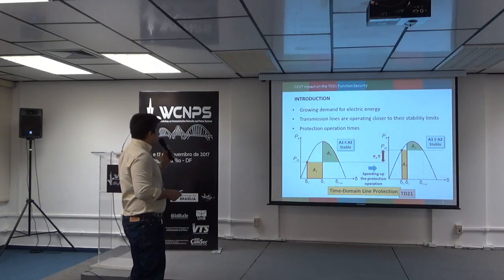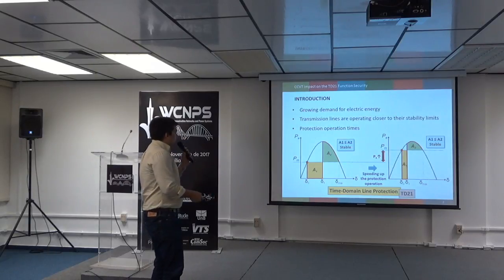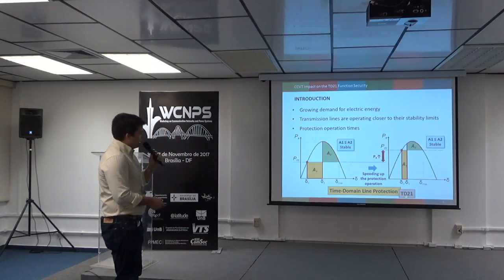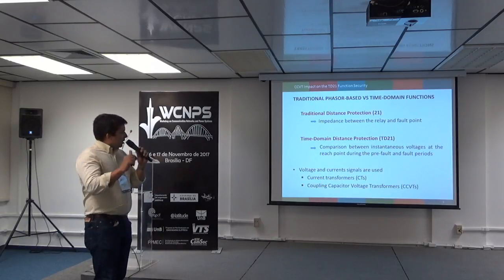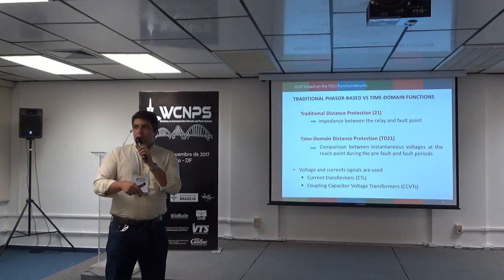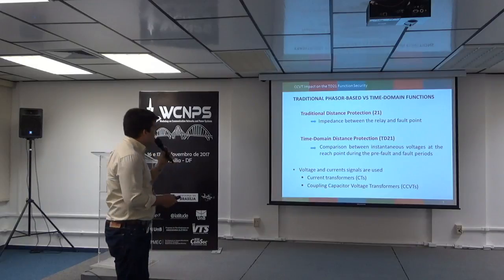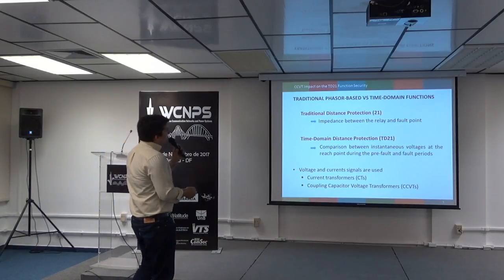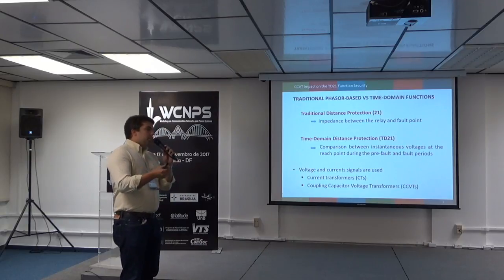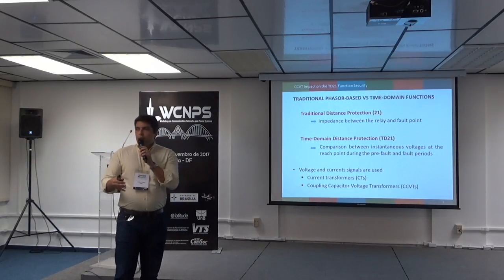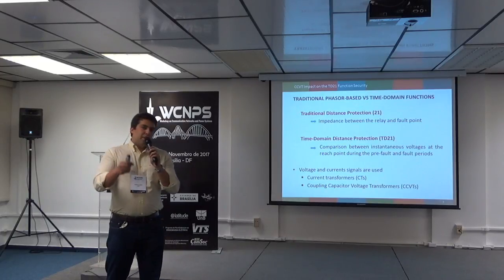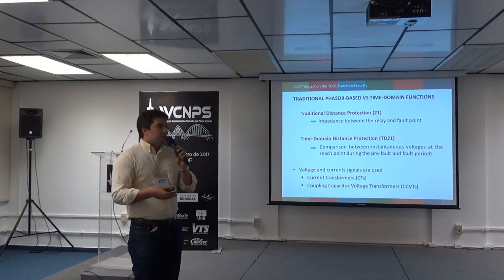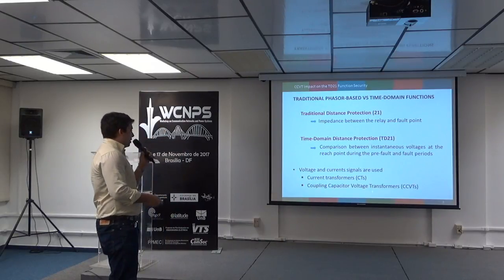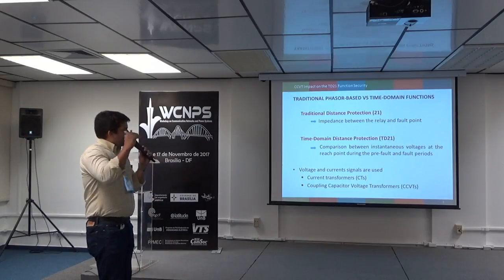In this paper, as I said previously, we are analyzing the distance protection applied in time domain, which is called here TD21. Let's talk a little bit about the traditional distance protection function and the time domain distance protection function. It's well known that the traditional distance protection function is based on the impedance measured between the relay and the fault point. To do so, we usually use voltage phasors and current phasors, so we have to use current transformers and coupling capacitor voltage transformers if your system is a high voltage system.